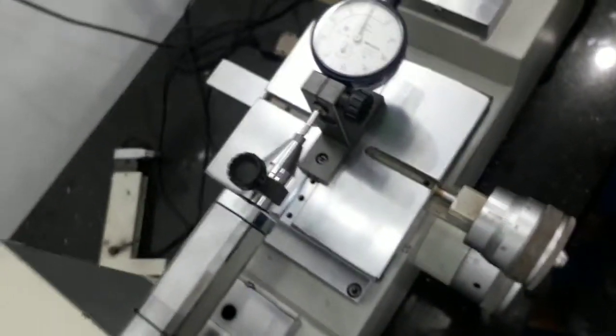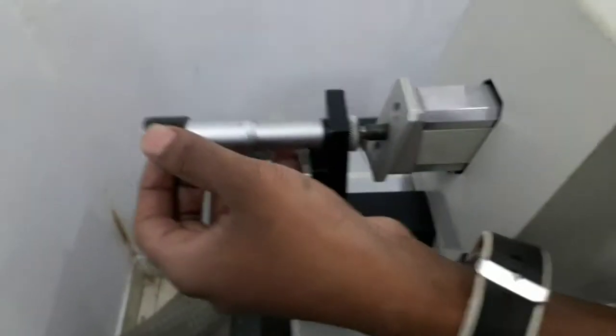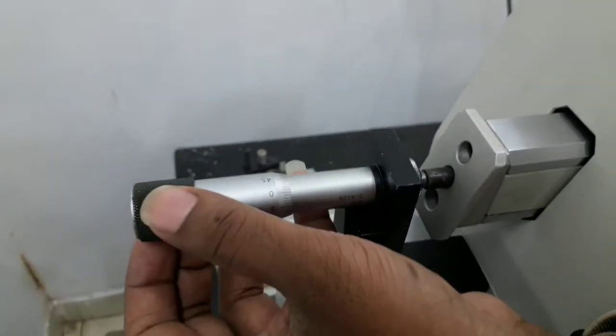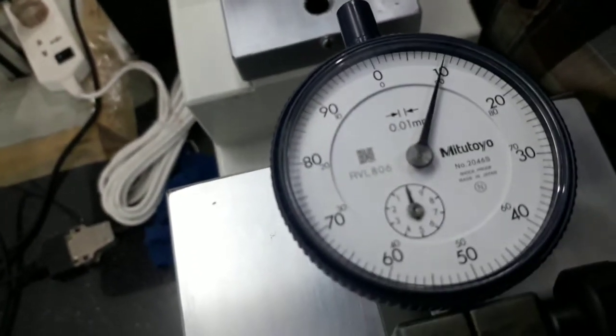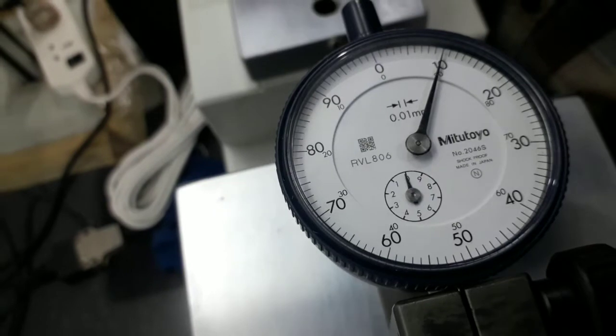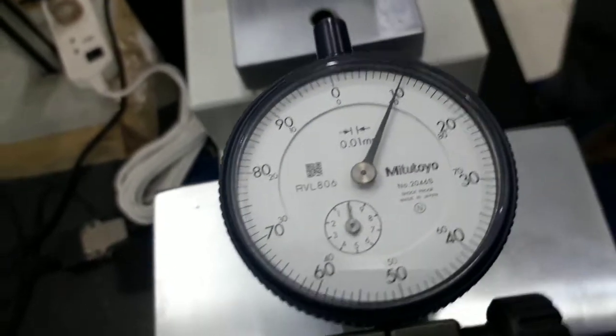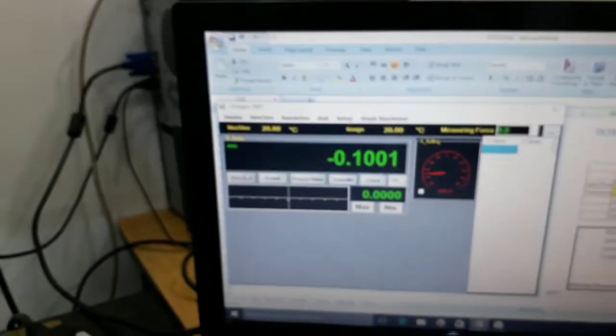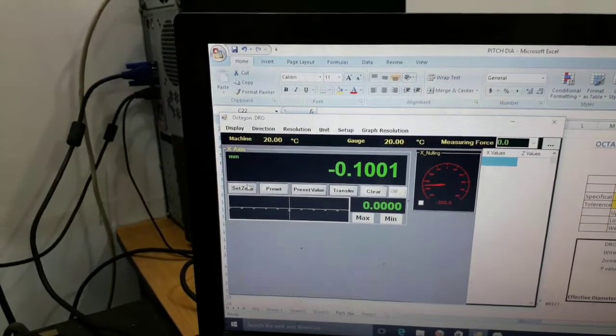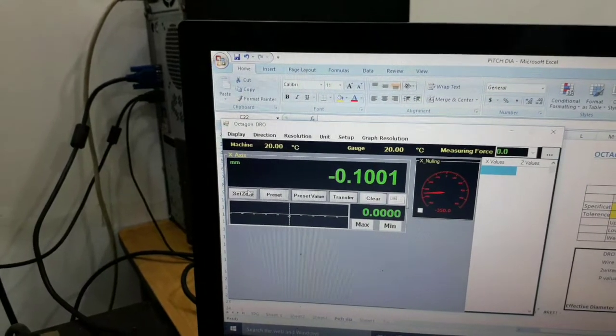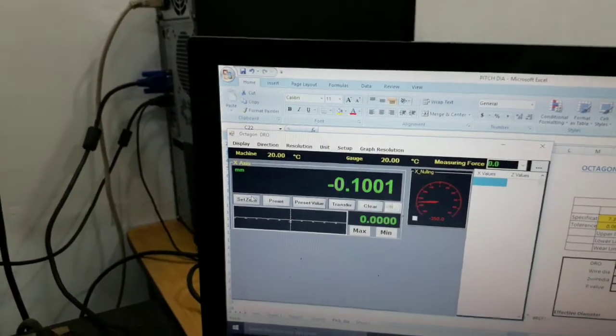Now this DUC is also zeroed, and the digital DRO is also zeroed. Now incrementally we change this spindle - by operating this micrometer you can move the spindle very slowly, so that it is now reading 10. That means the least count is 10 micron, so it is 100 microns. Then what is the deviation here? You can see it is 0.1001, meaning there is a deviation of only 0.1 micron.